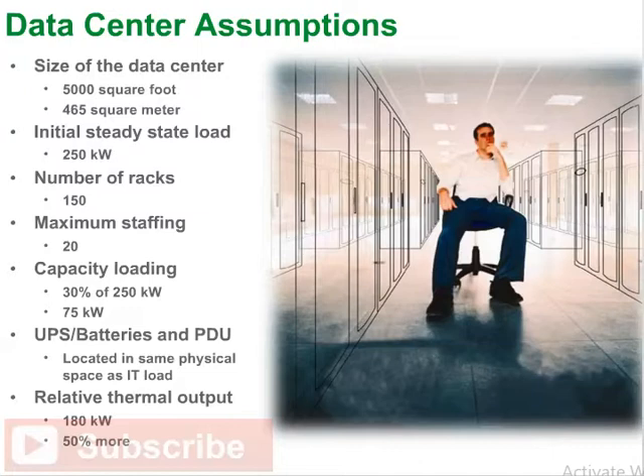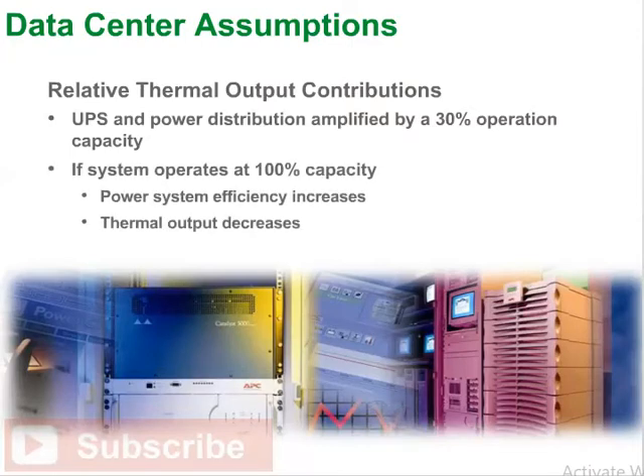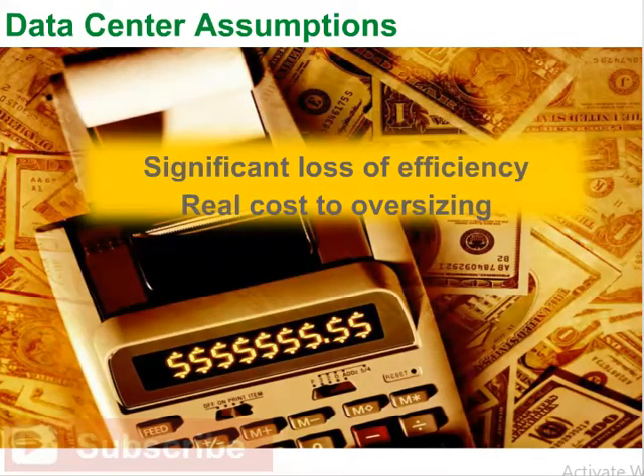For this example, it is assumed that UPS batteries and PDUs are located in the same physical space as the IT load. The thermal load is 180 kilowatts, which is 50% more than the IT load. Note that contributions to thermal output from the UPS and power distribution are amplified because the system is operating at only 30% of capacity. If the system were operating at 100% capacity, power system efficiency would increase and their relative thermal contribution would decrease.